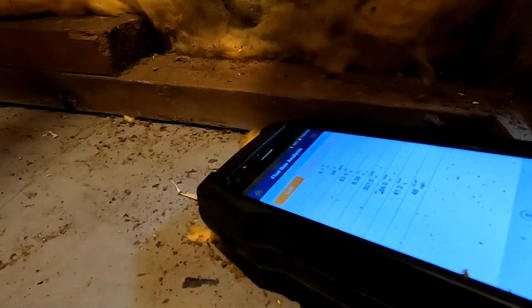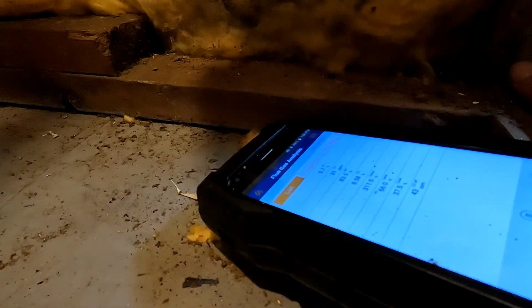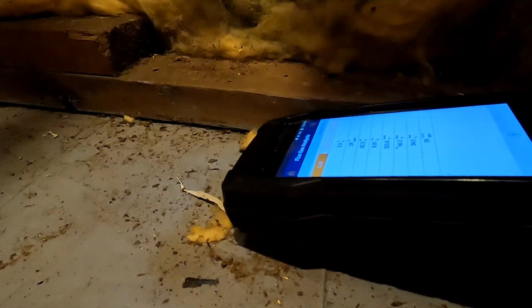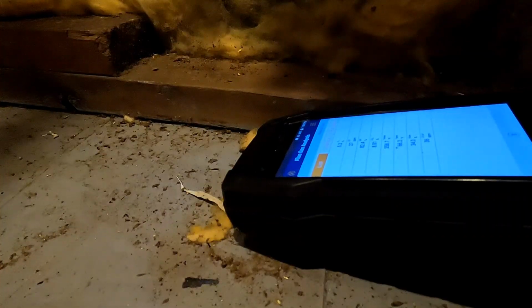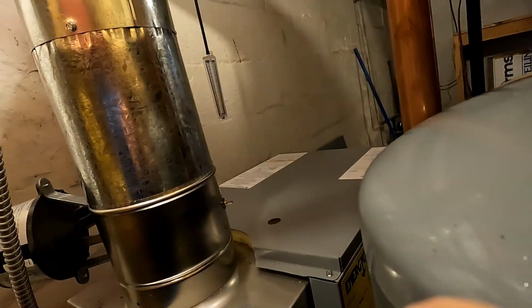Now these hydrostats, I think they're called the 4200. They make the 3200, that is in a box. They're tuned to come on at 125 degrees, the circulator. So the burner will fire to heat up the water to eliminate condensation, and then it'll turn on the circulator until the water gets to 125. We do have a good draft. I don't know if you can see that over there. It's moving. It's about a 1.5.